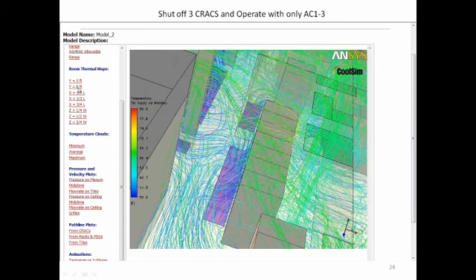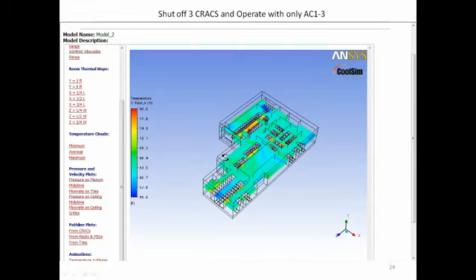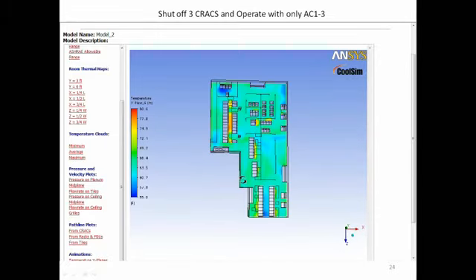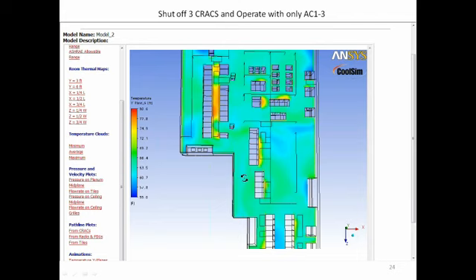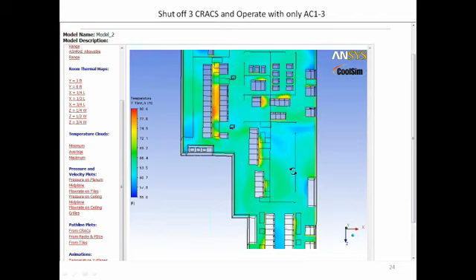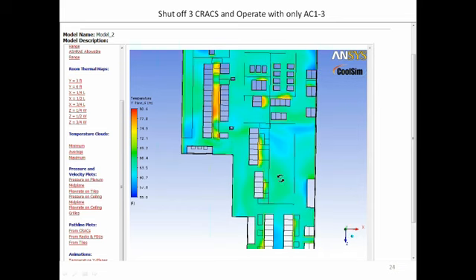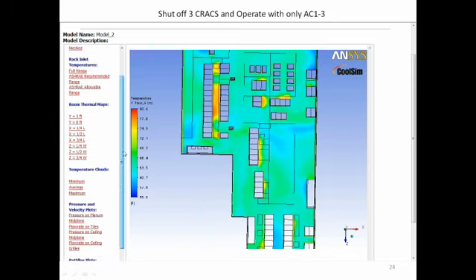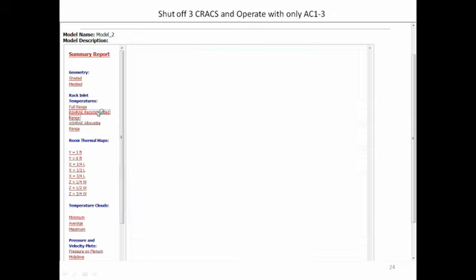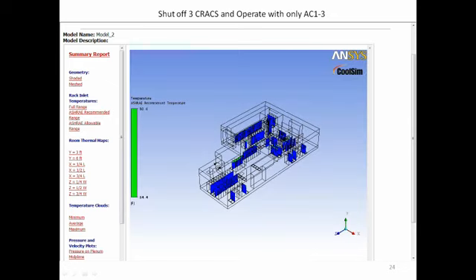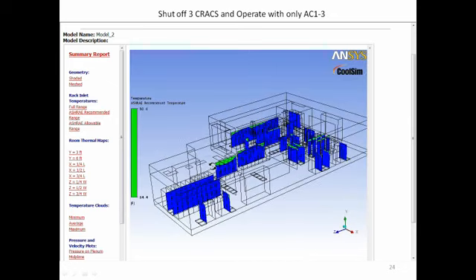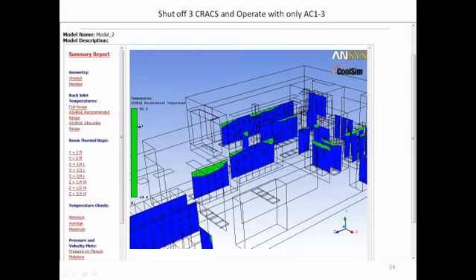If you look at your cut planes here now at 6 feet, a lot of people like to stare at these. This is another representation. You can see that it's in much better shape than it was before with respect to temperature. Yep, it's hot in the hot areas, it's cooler out. If we take a look now at the rack inlets, we see in our chart that we're beginning to come into compliance in certain areas.